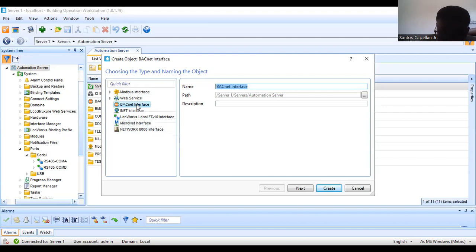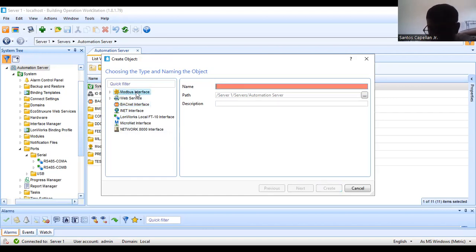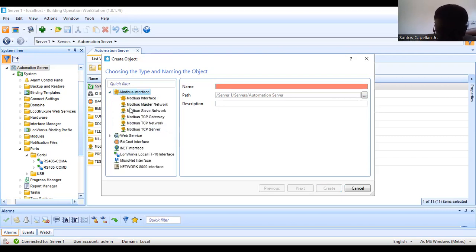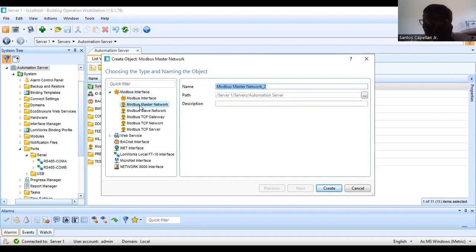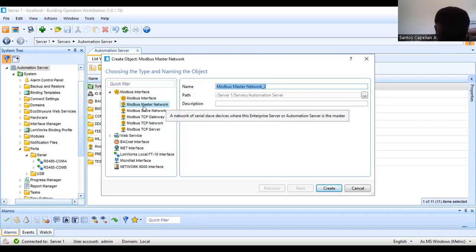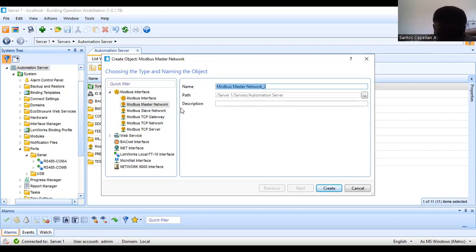There are different interfaces available. I have shown you the BACnet interface in my previous tutorial. Here we will be doing the Modbus interface, because the communication protocol used by our communication module is Modbus. We will create the Modbus master network because my automation server will act as the master, and the connected devices will act as slaves. I already created one — let me just show you the created Modbus interface.